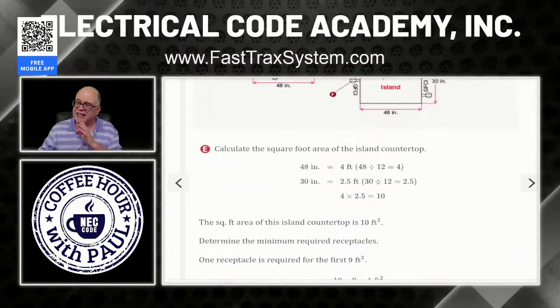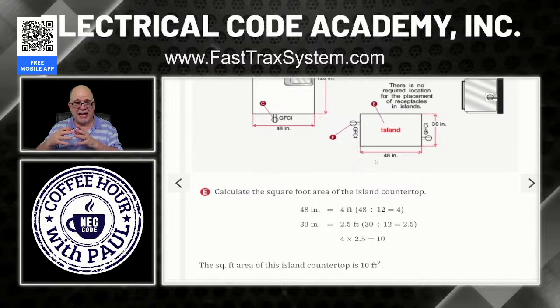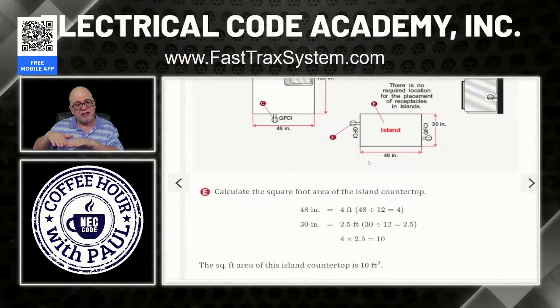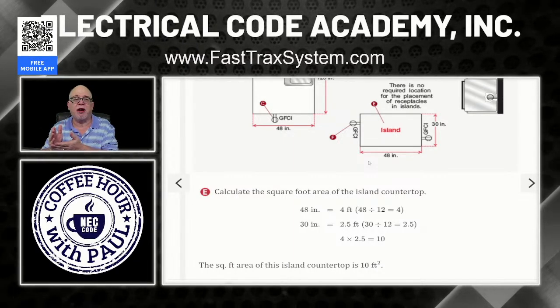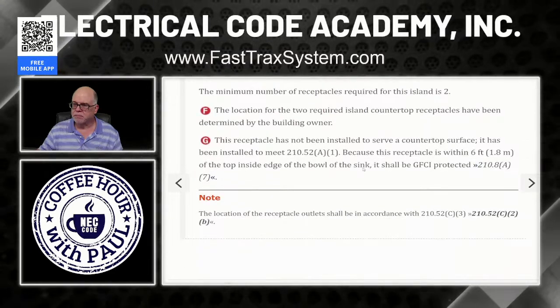Now, on this island, since it's flat across the entire surface, you are permitted to either put it in the island. You can pop it up, again, it could pop up above it. But it also can be below the countertop as long as it's not more than 12 inches below and it's not under an overhang that is more than 6 inches from the base. If it isn't, then we can put it down on the side. And that's what it tells us right here.